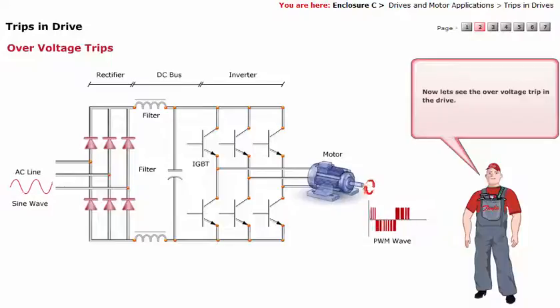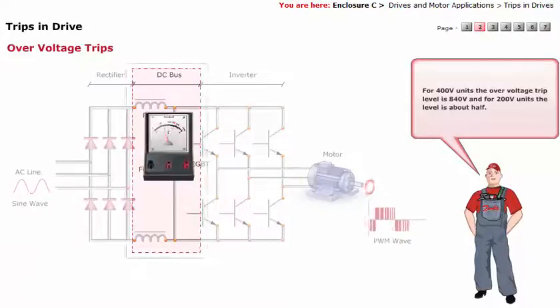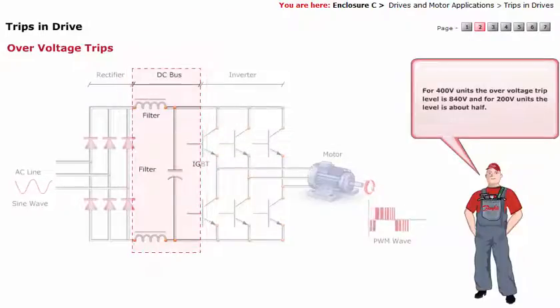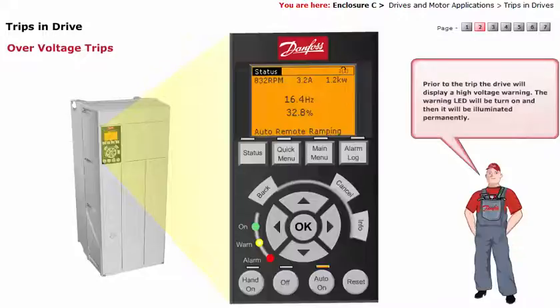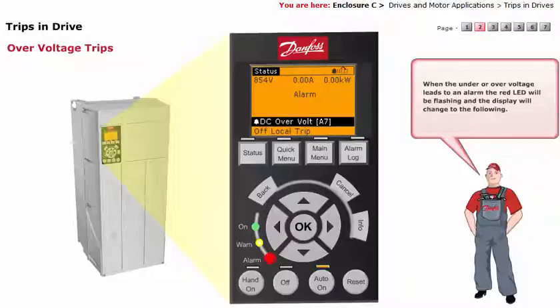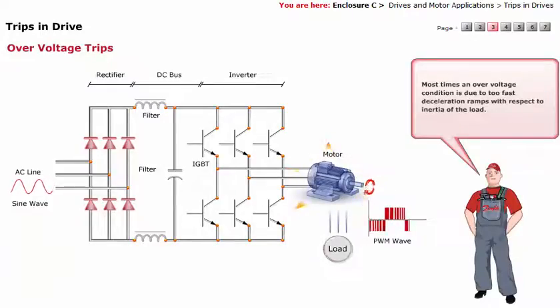Now, let's see the over voltage trip in the drive. For 400 volt units, the over voltage trip level is 840 volts, and for 200 volt units, the level is about half. Prior to the trip, the drive will display a high voltage warning. The warning LED will be turned on and then illuminated permanently. When the under or over voltage leads to an alarm, the red LED will be flashing and the display will change accordingly. Most times, an over voltage condition is due to too fast deceleration ramps with respect to the inertia of the load. During deceleration of the load, the inertia of the system acts to sustain the running speed.